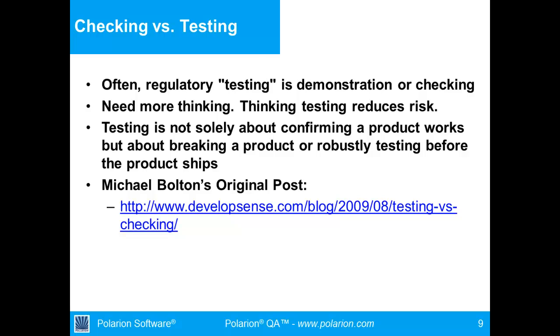If you only have checks, most auditors, if they're following FDA regulations, you have a requirement, you have some type of check that confirms that the requirement was designed and implemented, and then you have evidence that shows that. That will usually satisfy them, but while it may be technically regulatorily compliant, it doesn't necessarily address the risk issues. So you should always be thinking about that.